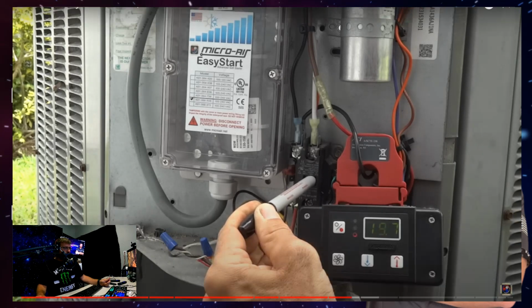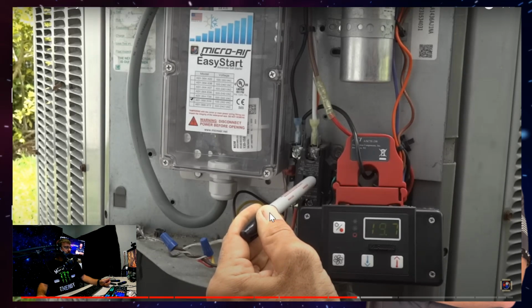God, that fan motor sounds horrible. We've got 19.7 amps for a peak starting current. That is almost a 75% reduction from that original 77.4 amp peak that we saw without Easy Start installed. So that's just kind of like a brief video of how it works.